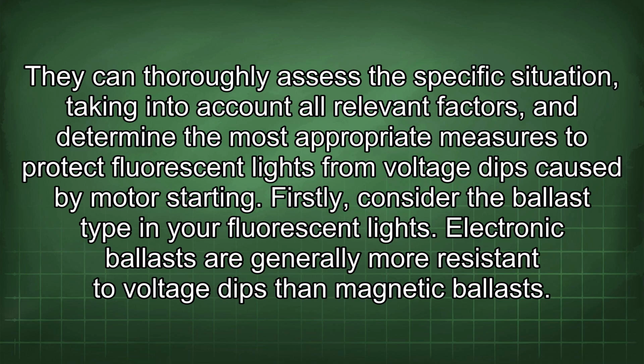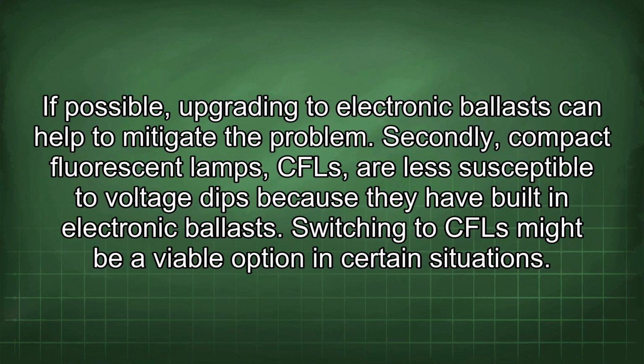Firstly, consider the ballast type in your fluorescent lights. Electronic ballasts are generally more resistant to voltage dips than magnetic ballasts. If possible, upgrading to electronic ballasts can help to mitigate the problem. Secondly, compact fluorescent lamps, CFLs, are less susceptible to voltage dips because they have built-in electronic ballasts. Switching to CFL might be a viable option in certain situations.